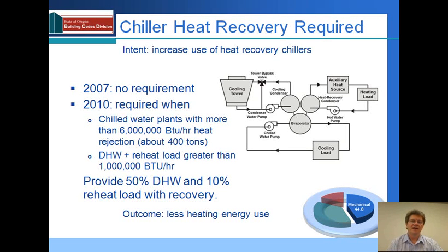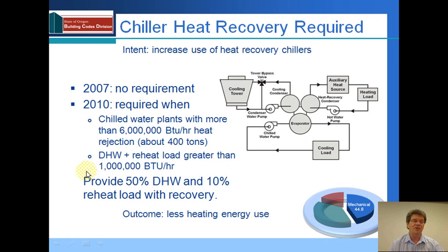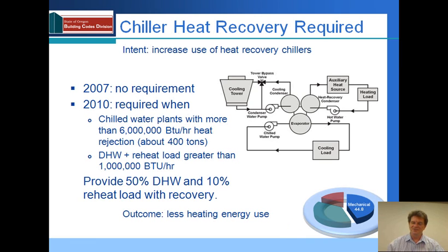Chiller heat recovery is now required — a new requirement on larger systems above 6 million BTUs per hour, which is a chilled water plant of about 400 tons, with a combined domestic hot water and reheat load greater than a million BTUs per hour. In this situation, half of the domestic hot water load and 10% of the reheat load must be met by recovered heat from the chiller. The outcome is that instead of throwing that heat away at the cooling tower, we recover it and reduce energy use at the boiler.